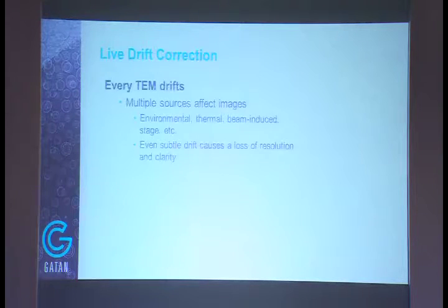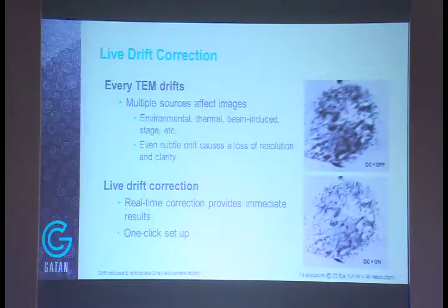And so what's really interesting about this camera is we've integrated live drift correction into this particular camera. So when you're collecting images with a camera, if there's any motion of the sample, and that can actually happen with plastic sections, there'll be slight motion, you can start to try and correct for this motion so your images look sharp. And I'm going to give you an example of this in the next case here.